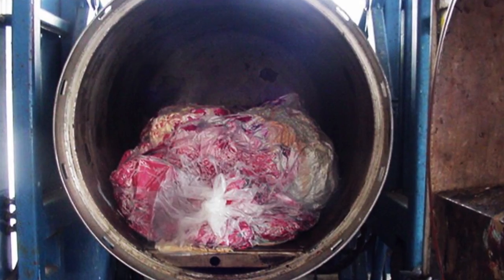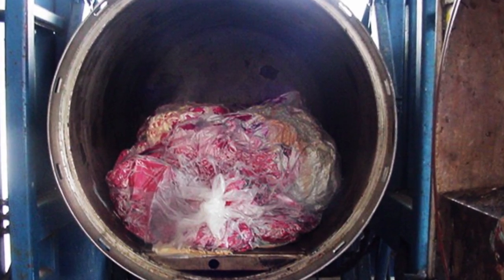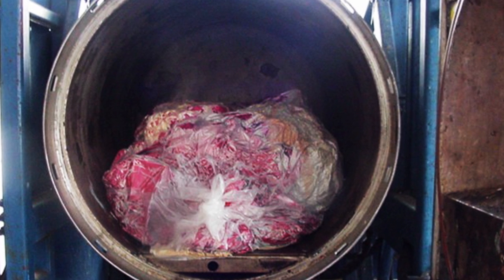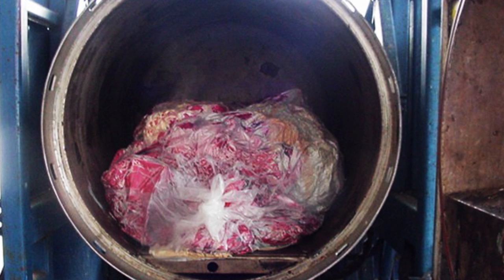If shredding, macerating, or breaking up the infectious waste is ever to occur, it should only happen after the waste has been fully sterilized to avoid potential aerosolization of deadly pathogens. Alarmingly, some technologies break open the infectious waste prior to sterilization and create harmful exposure when the blades, augers, or shredders require servicing. All SANIPAK units only shred or compact after the waste has been fully sterilized.